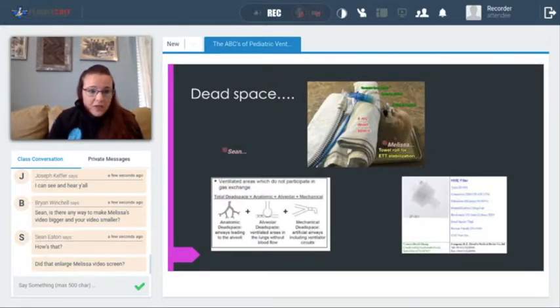I saw a couple other pictures where people tape the BVM to their chest so they always know where it is in case of an emergency, but then they secure their vent tubing on there. You don't want any tension pulling on that ET tube because it's not going to be where it needs to be. And then depending on what kind of ventilation setup, like this blue adapter right here is a flow sensor. A lot of our really good ventilators have a good flow sensor like that. You have to calibrate early on in your transport, but that's going to add some dead space. In here, they don't have, which we all transport with, is our end tidal adapter. So that's going to add some more.